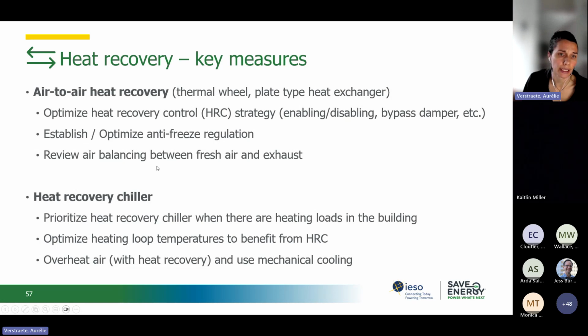For the heat recovery chiller, as discussed, you want to prioritize it when there are heating loads in the building. You want to optimize heating loop temperatures, and you also want to overheat air when you have air-to-air heat recovery in the building. So you can use mechanical cooling and benefit from a good COP for heating.